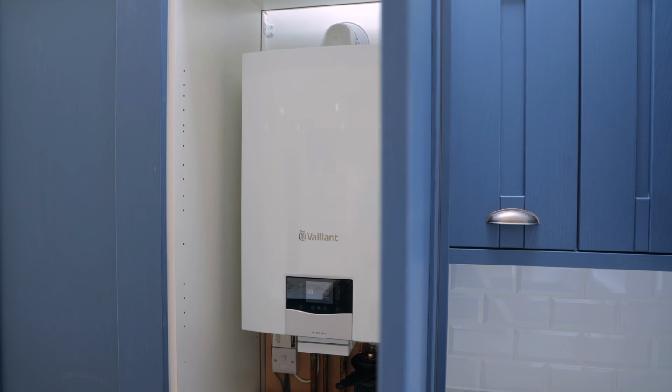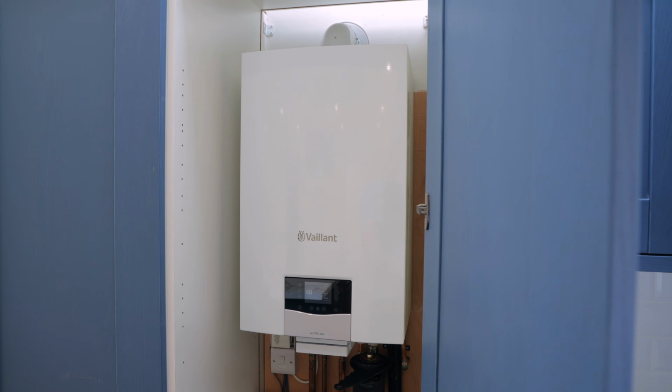We can also look at diagnostic information. Diagnostic information can allow us to look at what's actually happening in a little more detail. We can look at things such as the domestic hot water flow rate, temperatures and fan speeds, and lots of other useful information, and that's all done through the diagnostic codes. Now again, please note that because some of these parameters can be modified, it's very important that only a gas safe engineer with an awareness of what those codes are makes any changes.